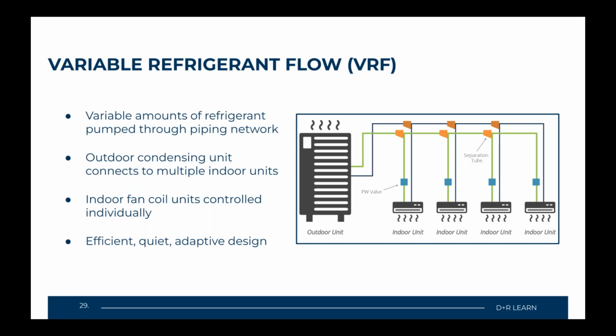All right, so here we have variable refrigerant flow, VRF systems. And VRF, once again, stands for variable refrigerant flow, and this is exactly how these systems operate. Now, you may be familiar with a term which is referred to as VRV, or variable refrigerant volume. This is just a Daikin brand-specific name for VRF systems, and it is another term that you may hear out there in the field. You'll either hear VRF, but very rarely will you hear VRV, which stands for variable refrigerant volume.